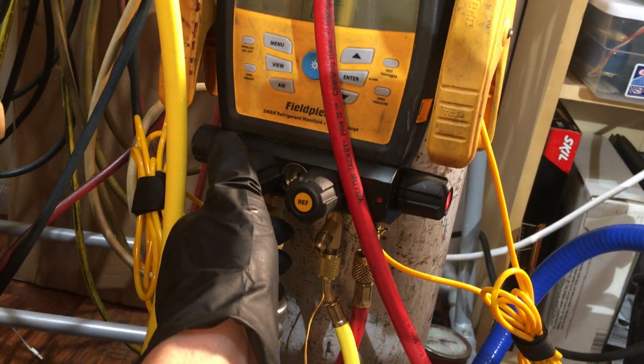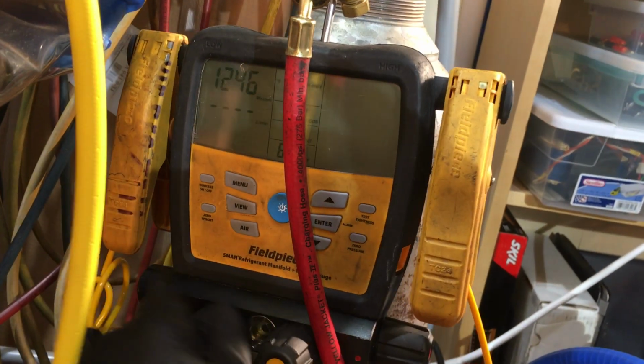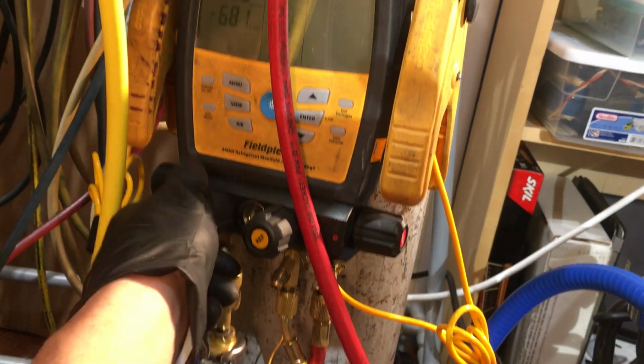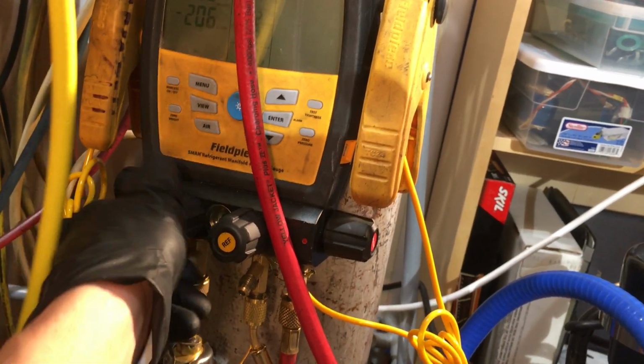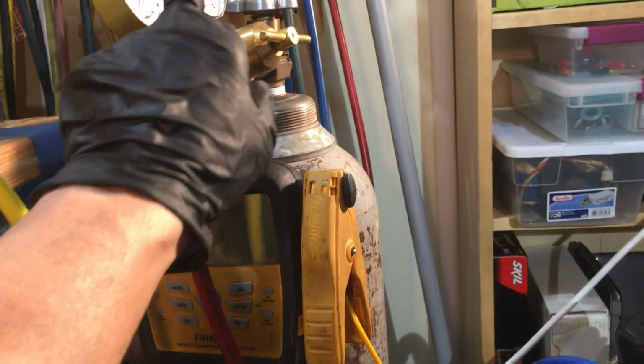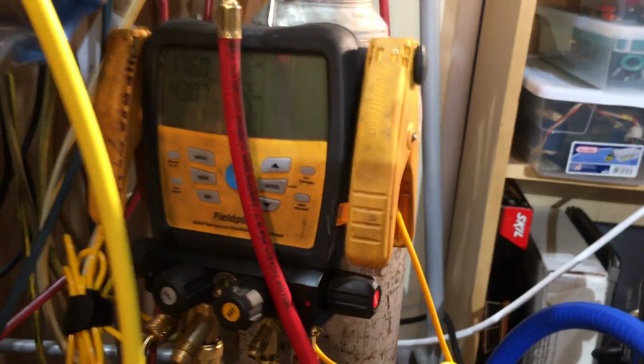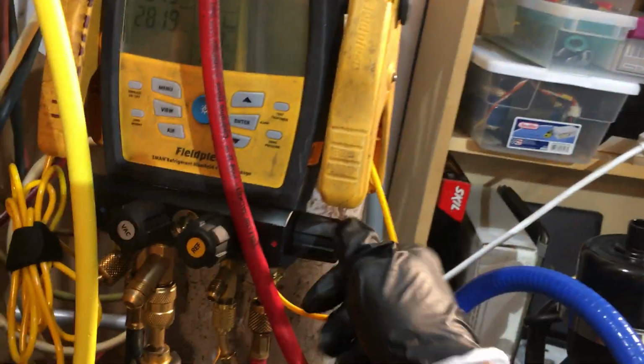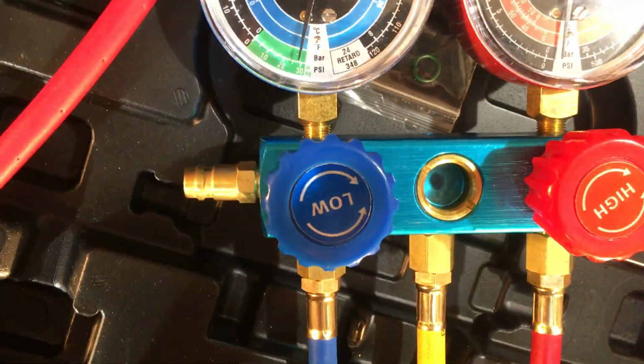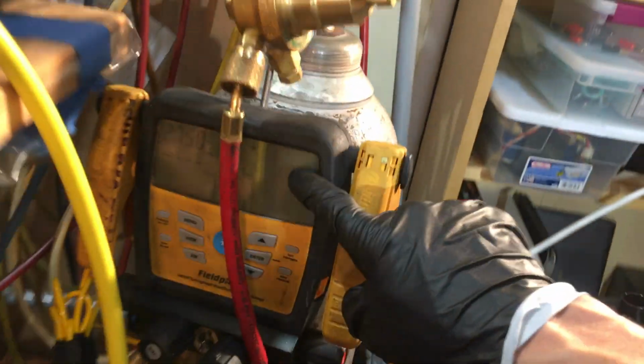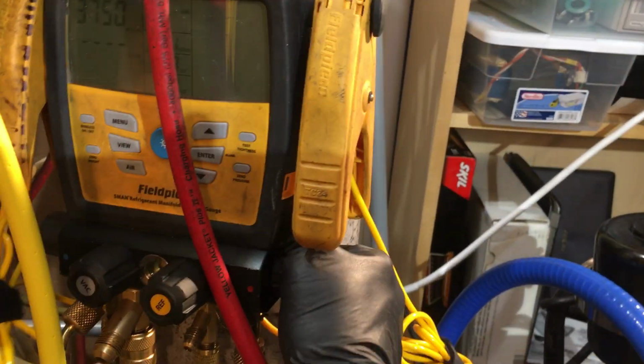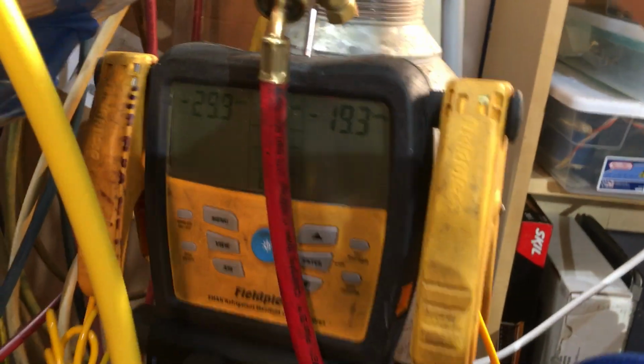So let's turn back on the vacuum, get it back down. There's a lot of moisture inside these hoses, real cheap. And we're going to do a pressure test. So let's turn off the vacuum source. And now we're going to turn on our 250 PSI of dry nitrogen, which we'll see the pressure here on the high side once I open it up. And so we're still in the 29 vacuum. And now you're going to watch this jump up. Open up the pressure.